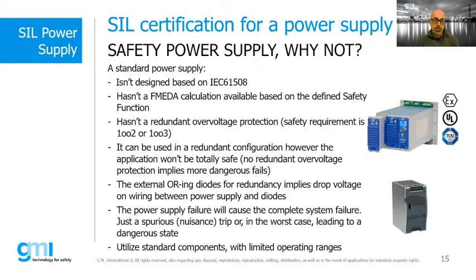And also, standard power supplies often require external OR-ing diodes to allow for redundancy. This means adding external wiring that, especially for high load currents, creates a high voltage drop which has a strong impact on the supply voltage. It's true that it's possible to adjust the output voltage to compensate for the voltage drop, but this operation increases consumption considerably. In addition, a standard power supply has a higher number of spurious faults than a safety power supply.